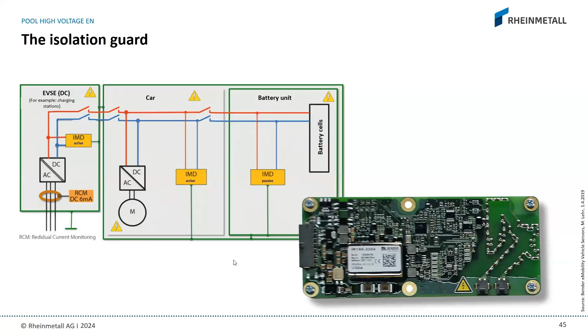On the battery unit, we have a passive system, which means it uses 3 voltmeters to ensure more precise measuring of the units. This is only used in the battery itself. We see here why: we are measuring with voltmeters between the line plus, high voltage plus, and PE, and between the voltage minus, high voltage minus, and PE - we have 2 voltmeters there, and a voltmeter between plus and minus directly.